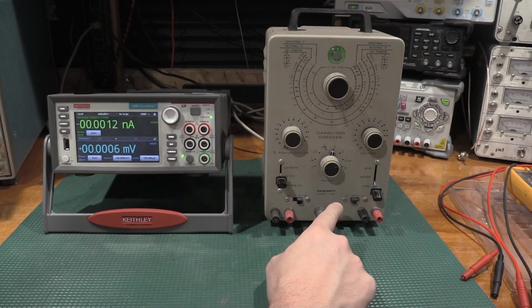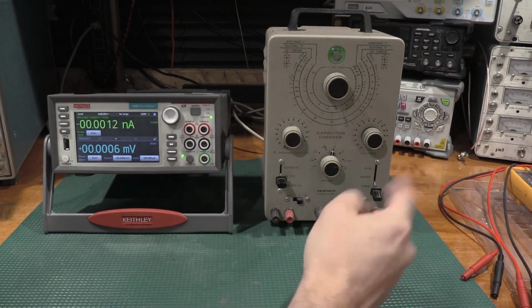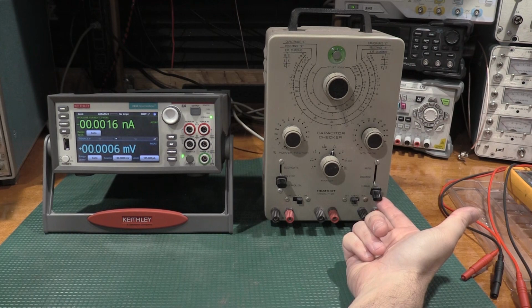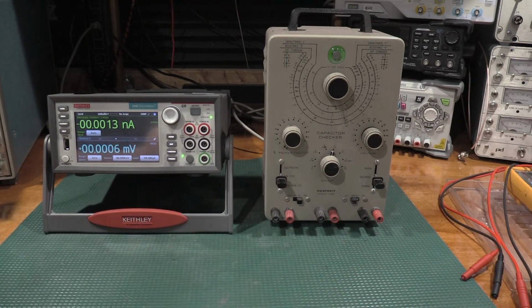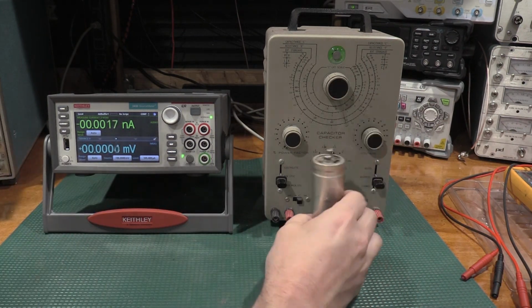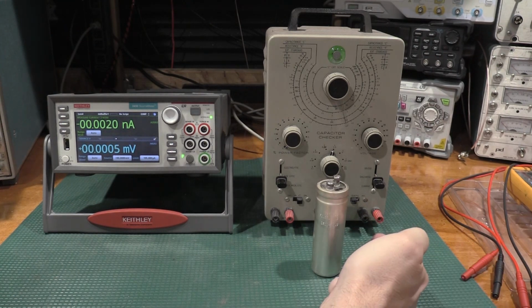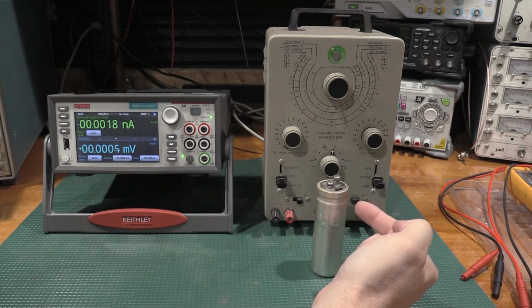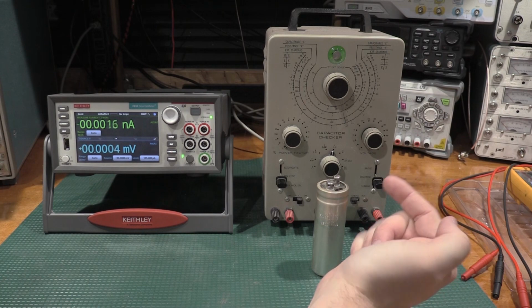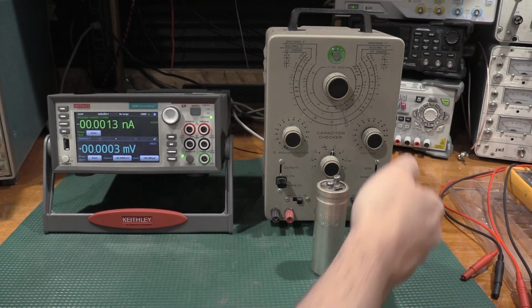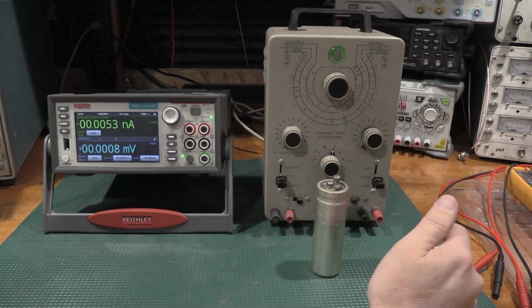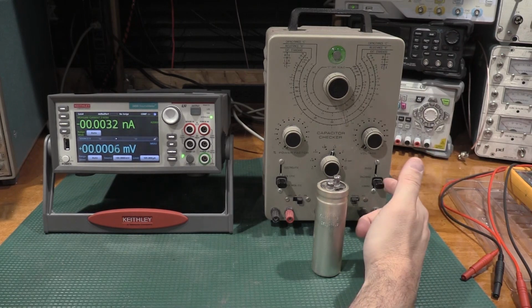Actually, more than that, which is why I'm going to get into a problem with this thing in a minute. So you have to be really careful, especially if you put a large capacitor right there. Now you've got 600 volts with a charged capacitor at 600 volts. Stuff's starting to get spicy. So always bring this back down and leave it in the discharge mode.